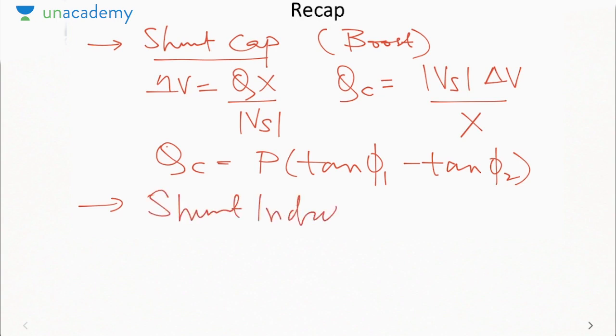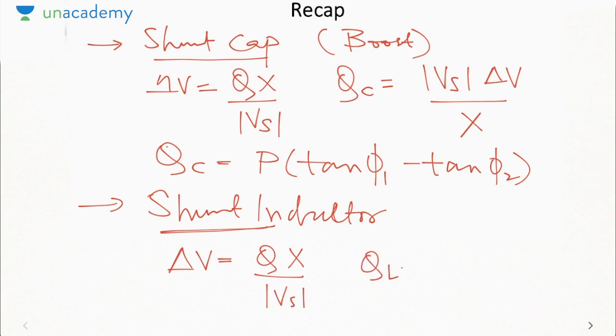In shunt inductor, we saw it is used to correct over voltages in the system. Hence, it is used as a Ferranti effect control device. Here also delta V was given by Q into X by mod Vs, due to which rating of the inductor would be mod Vs into delta V by X. Okay, and it can also be used for power factor correction, but for the leading power factor loads. So shunt capacitor is used for lagging power factor loads, whereas shunt inductor is used for leading power factor load.